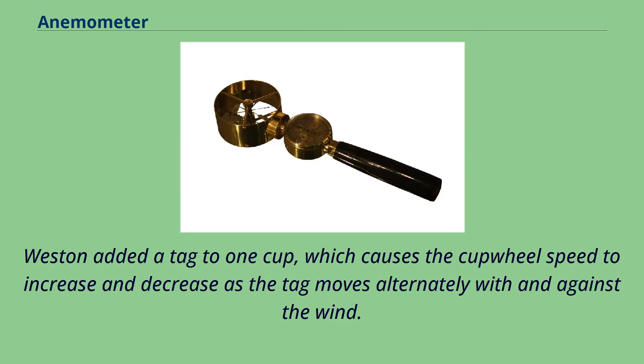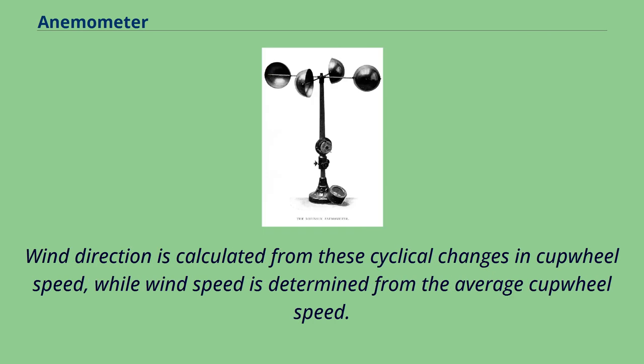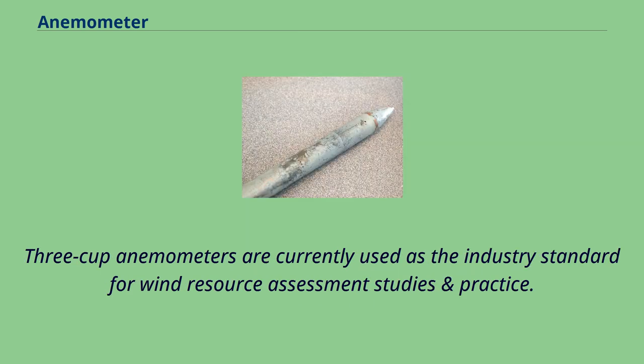The three-cup anemometer was further modified by Australian Dr. Derek Weston in 1991 to measure both wind direction and wind speed. Weston added a tag to one cup, which causes the cup wheel speed to increase and decrease as the tag moves alternately with and against the wind. Wind direction is calculated from these cyclical changes in cup wheel speed, while wind speed is determined from the average cup wheel speed. Three-cup anemometers are currently used as the industry standard for wind resource assessment studies and practice.